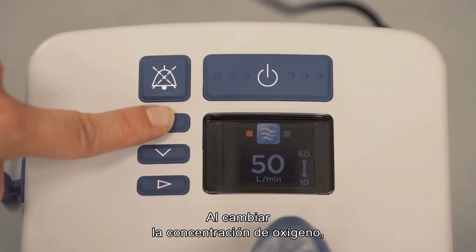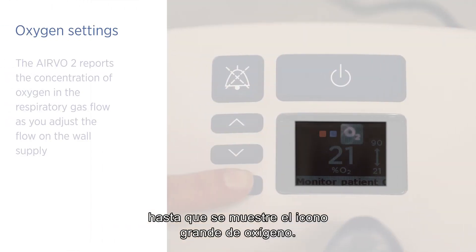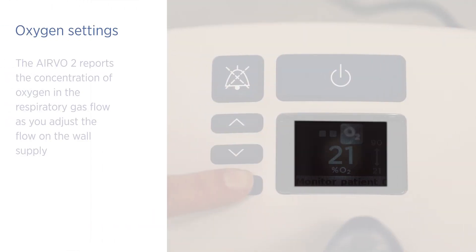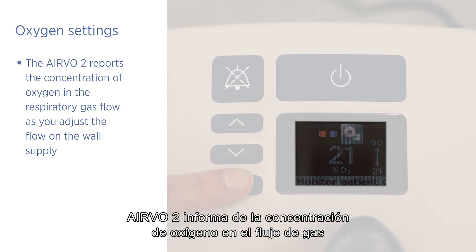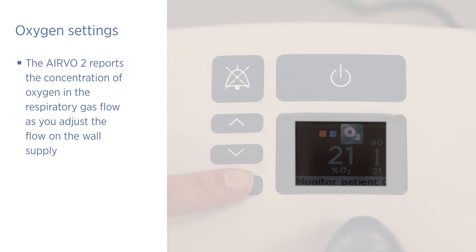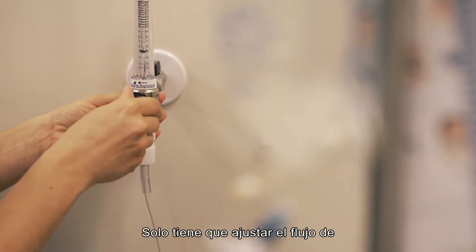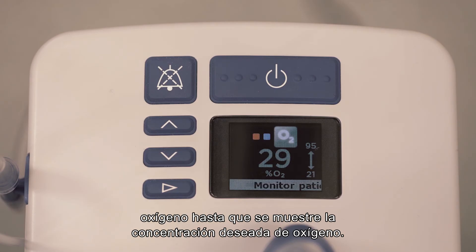When changing the oxygen concentration, press and release the mode button repeatedly until the large oxygen view is displayed. Using a built-in oxygen sensor, the AIRVO 2 reports the concentration of oxygen in the respiratory gas flow as you adjust the flow on the wall supply. Simply adjust the oxygen flow until the desired oxygen concentration is displayed.